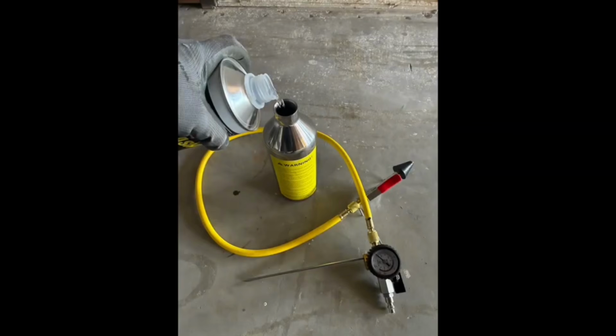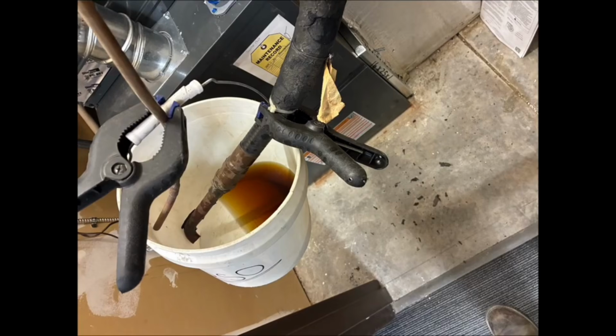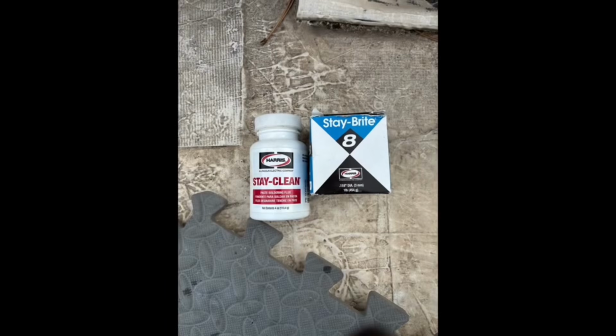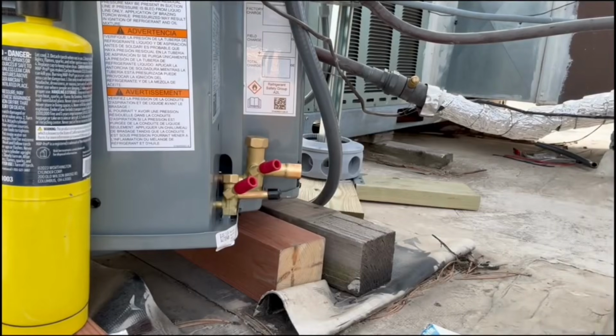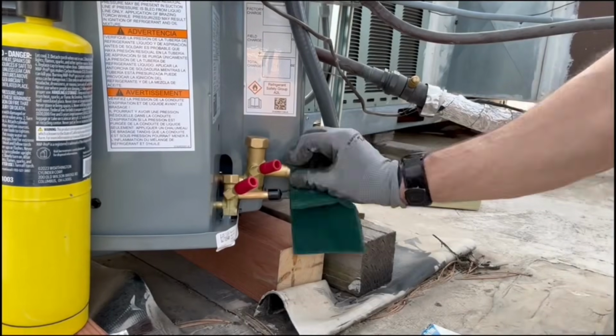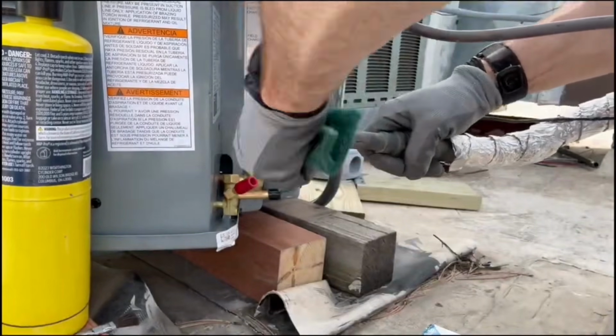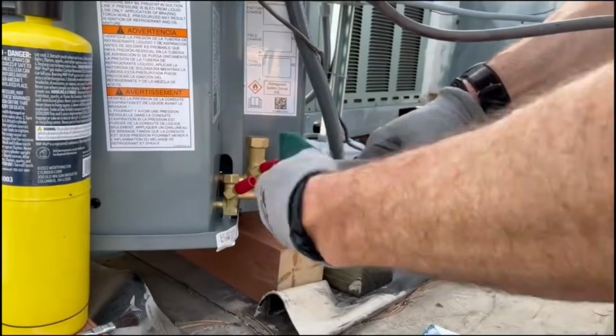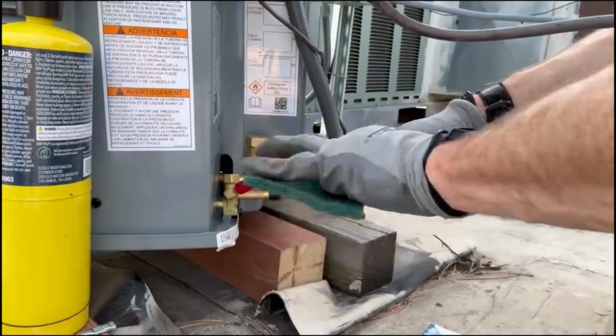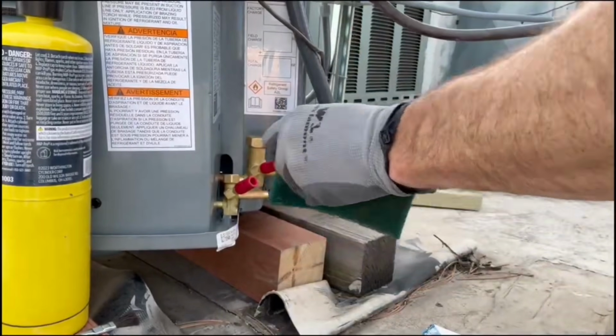Now I'm going to go ahead and clean the line set. You can see all the junk that came out of the old line set. So just did a line set flush. And you can braze or use this Stay-Brite 8 solder to reconnect your copper refrigerant line set. So I'm just going to clean everything off nicely on the new unit. I flux sparingly. You don't want to get a whole bunch of flux inside because you don't want the flux getting inside your compressor oil or your compressor, messing things up.